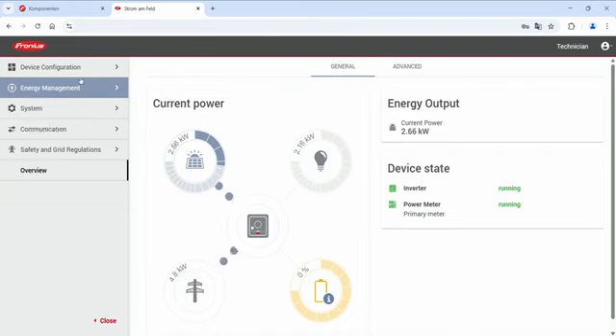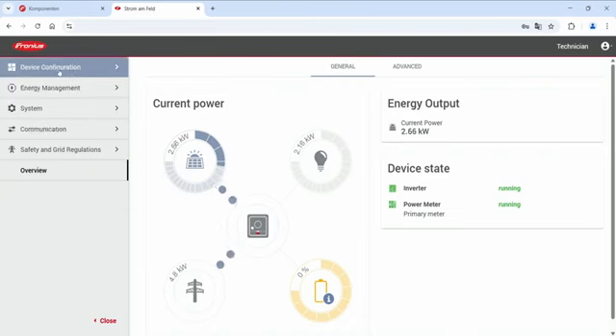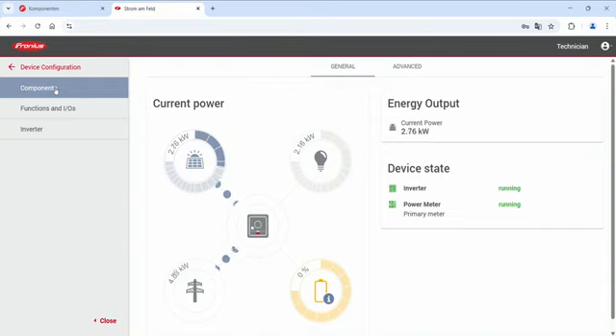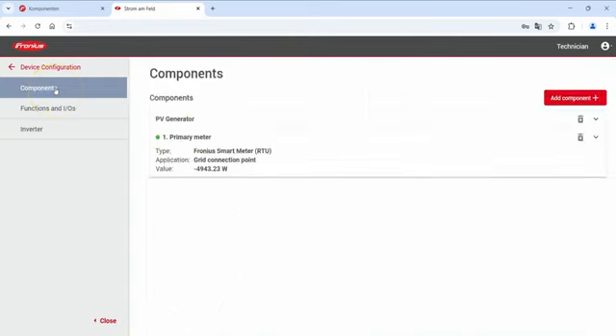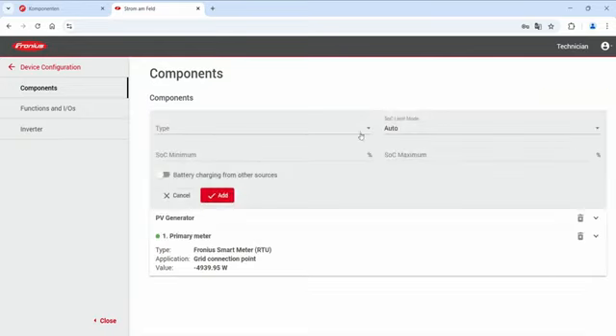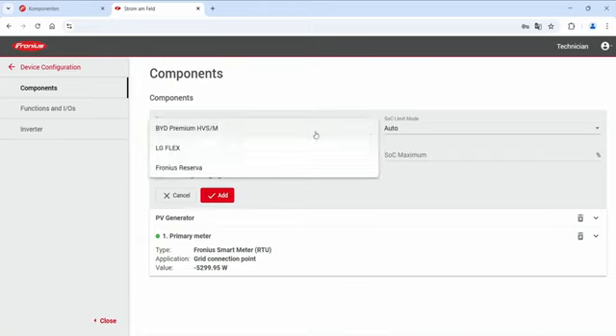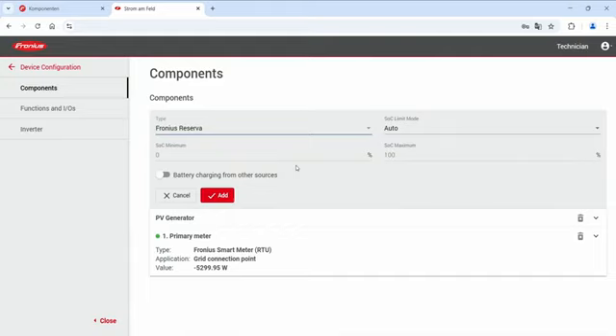After that, on the left-hand side, you will find the settings of the inverter, and there you can click on Device Configuration. After that, you click on Components. Here under Components, you at least need to add a primary meter so that the Fronius Reserva gets data from the hybrid inverter. After that, you can add a new component, and here you can add your new Fronius Reserva battery by clicking on Battery. After that, you choose the type of battery that you want to install, in our case the Fronius Reserva. And with that you can add the initial commissioning of the Fronius Reserva.